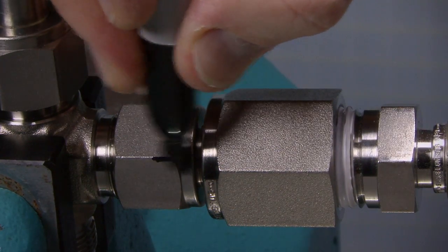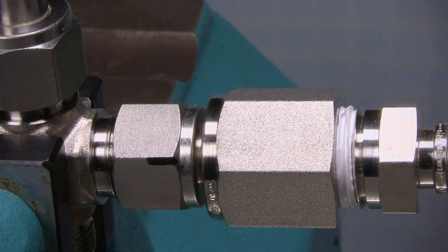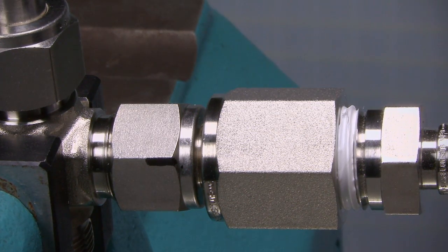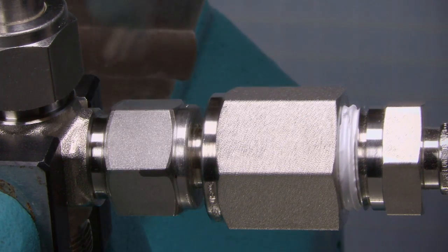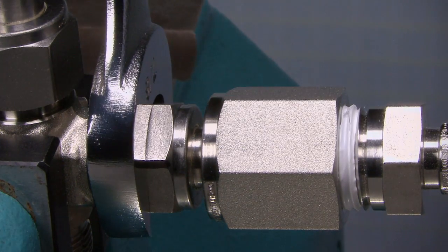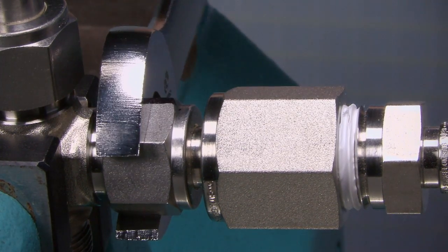Mark the nut at the six o'clock position. Marking the nut at six o'clock leaves no doubt as to the starting and ending positions. While holding the fitting body steady, tighten the nut one and one-quarter turns to the nine o'clock position.